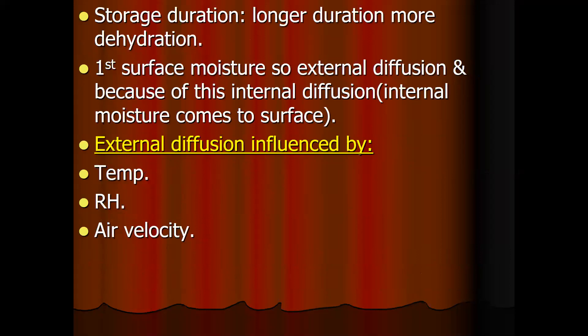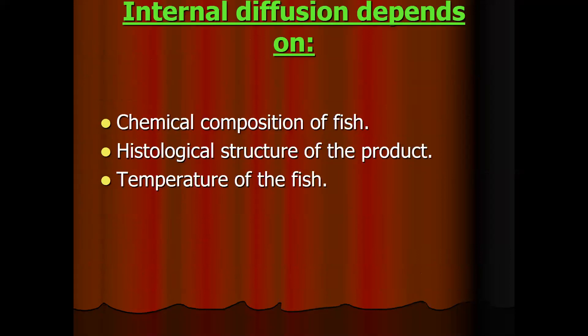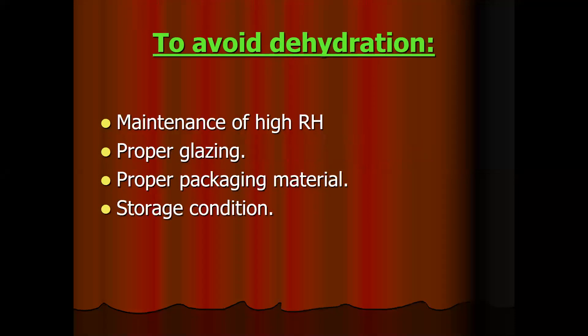Dehydration begins with the loss of surface moisture through external diffusion. Then internal diffusion causes internal moisture to come to the surface, which may change the quality. External diffusion is influenced by temperature, relative humidity, and air velocity — the storage temperature conditions. Internal diffusion depends upon the chemical composition of fish, histological structure of the product, and temperature of the fish. To avoid dehydration, we must maintain high relative humidity of 90 to 95 percent in the cold store and apply a protective treatment.